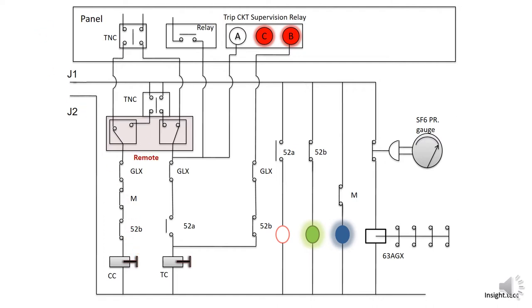Let's see how the breaker works remotely and locally. When the breaker is in remote position, it will operate from the panel — the TNC switch will operate from the panel. In local condition, this switch will convert so the TNC switch will not operate from the panel; instead the local TNC switch will operate. If the breaker is in local condition, it will operate from the local panel, and protection trip will also be active.